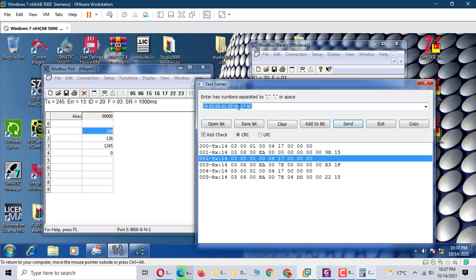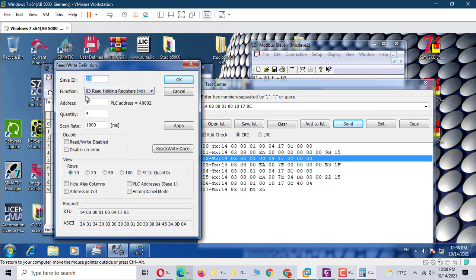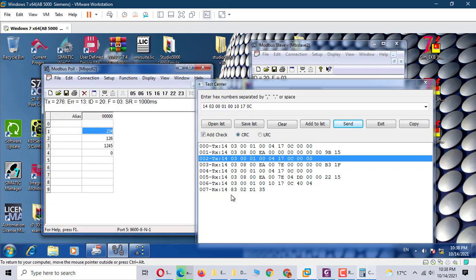If something is wrong, for example, if you ask a wrong address, what happens? He has a response that is an error. Look, it is 83. He responds 83. That is why we use function 3, and 83 means it's an error, something is wrong with what you asked.